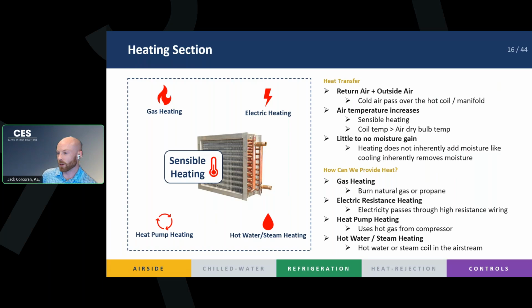Or you can have hot water or steam heating. These two are not part of a packaged rooftop, but it is worth noting because those are the other two ways you can get heating in your unit. Those two require a separate system, right? You can have a boiler, or Con Ed steam, or somehow you need to get hot water and steam, and that's not part of the packaged rooftop. That would be a separate system. If the building already has that available, you just add in a hot water coil to the packaged rooftop and call it a day.